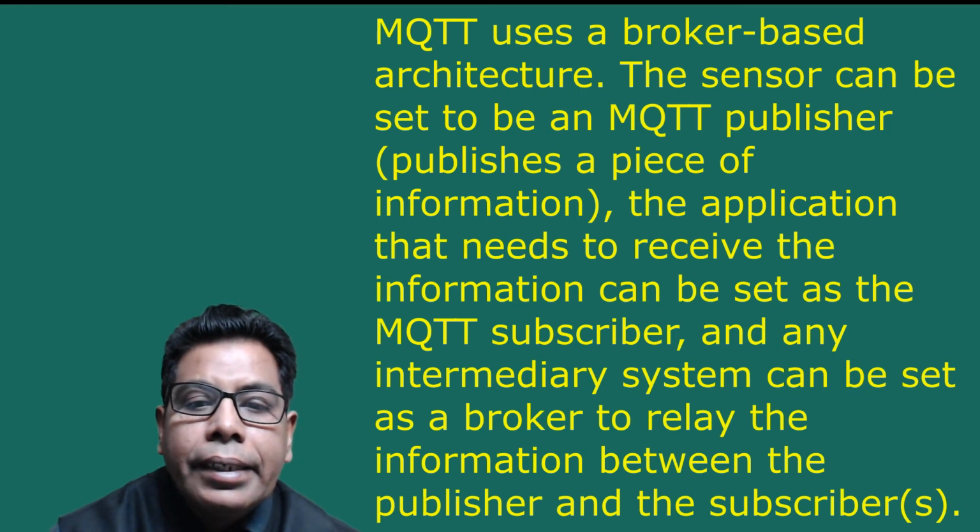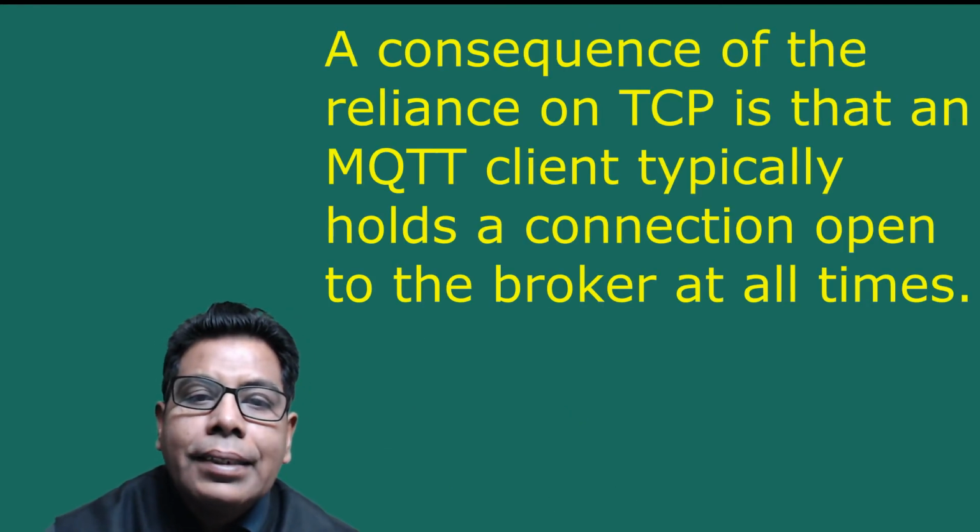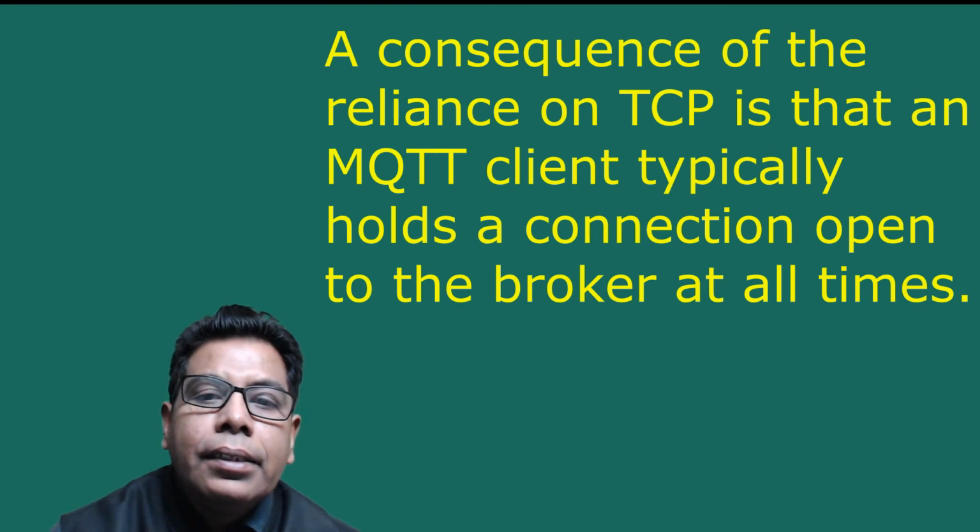The application that needs to receive the information can be set as an MQTT subscriber, and any intermediary system can be set as a broker to relay the information between the publisher and the subscribers. MQTT runs over TCP. A consequence of reliance on TCP is that an MQTT client typically holds a connection open to the broker at all times. This may be a limiting factor in environments where loss is high or where computing resources are limited.